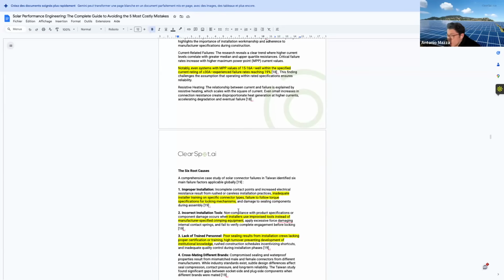Incorrect installation tools, maybe for speed, to cut the cost and reduce expenses, they didn't use the right tools instead of manufacturer-specific crimping equipment, which can either apply excessive force, damaging internal contact springs, or fail to verify complete engagement before locking. So EPC, if you're listening, take notes.